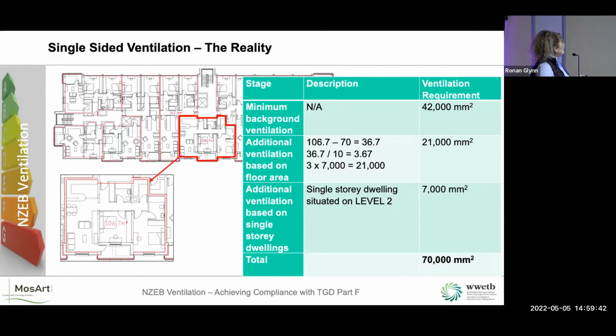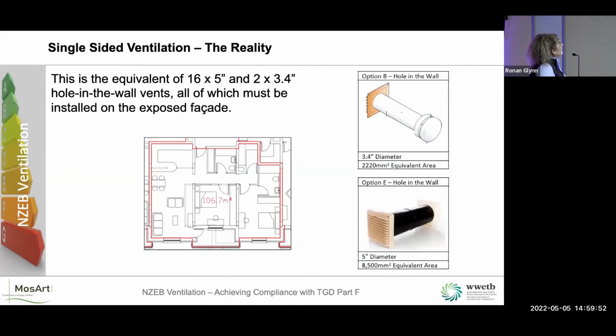For this little apartment, because there's only one exposed facade, there are apartments to the side, to the back, and to the other side, one above and another one below. When you do the ventilation requirement, it ends up that you have 18 holes in the wall. That's sixteen 5-inch vents and two 3.4-inch vents.